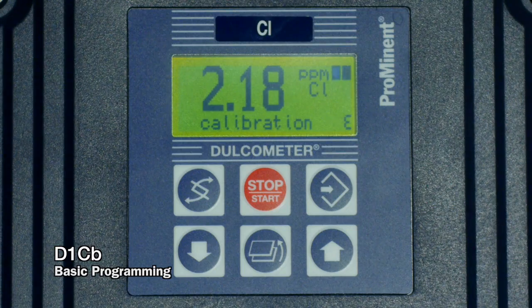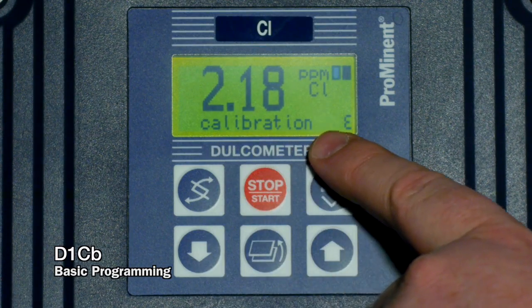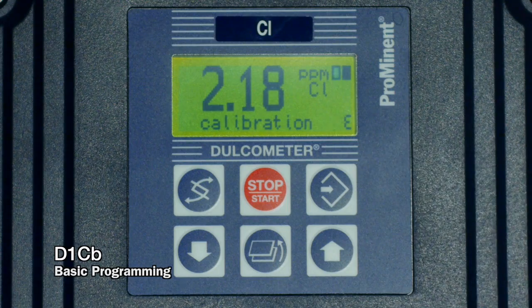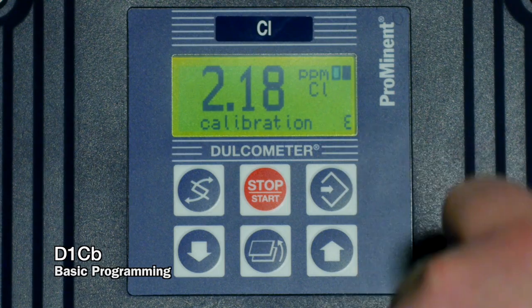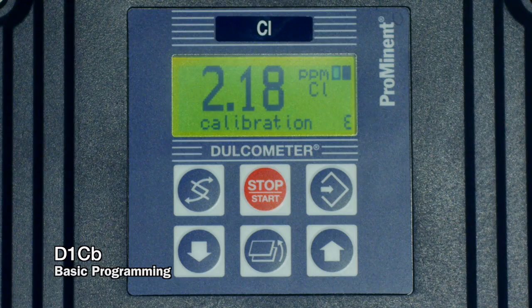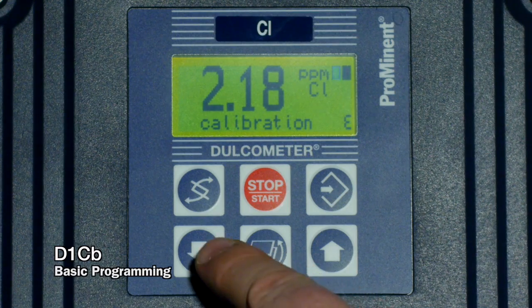The next step in basic setup would be to set up the calibration. You'll see that on a D1C-B, once you change the measuring range, or in this case we've also confirmed the type of sensor that we have, the first thing that it insists that you do is a calibration, and it will give you an error code on the far right hand bottom corner of the display until we do that calibration.